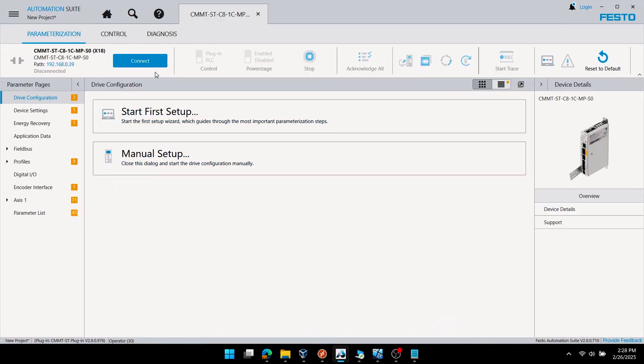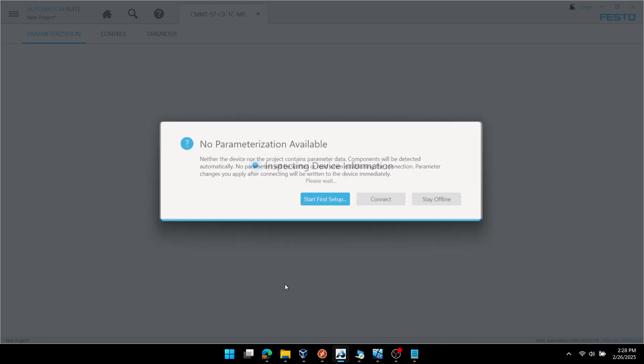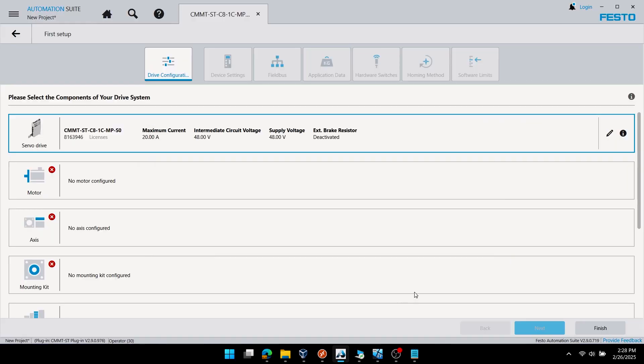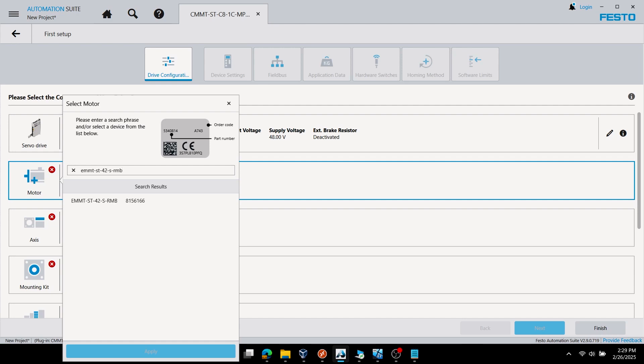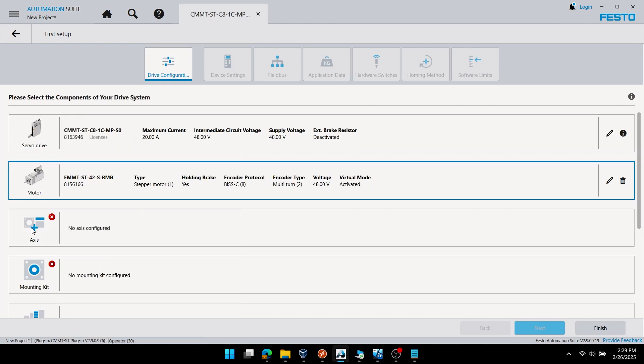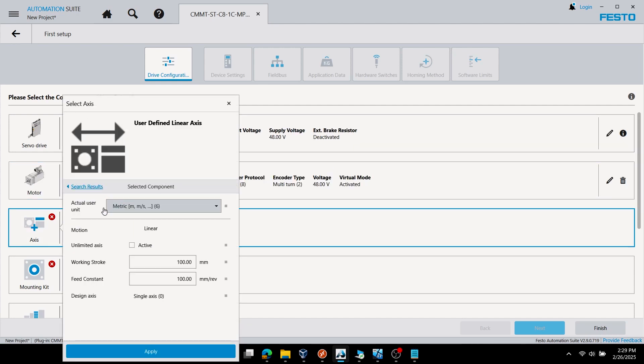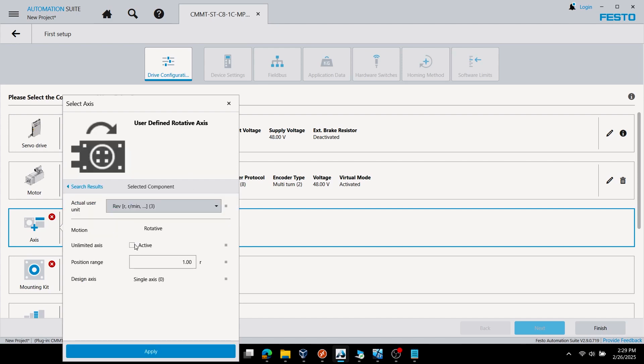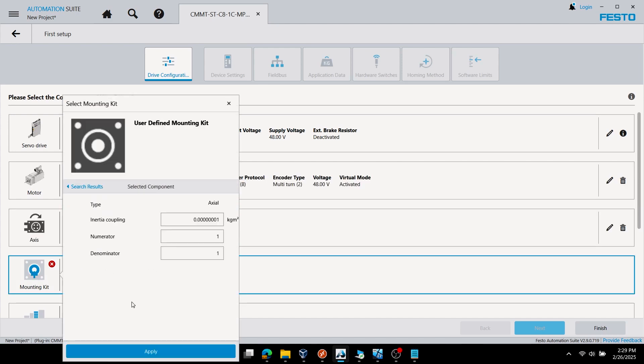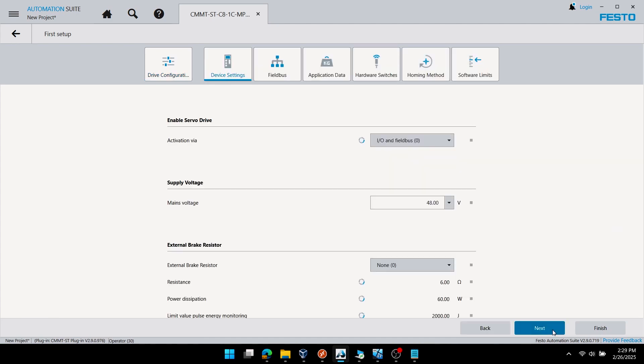Now I'll click connect. Since it's a factory default drive, it prompts me to start first setup. I'll click that blue button. I don't have a motor or axis here, so I'm going to use virtual today. I'm picking any motor and activating the virtual drive using a linear axis or rotary axis of unlimited rotations, and picking the user-defined mounting kit since I don't have that hardware. I just have the drive.